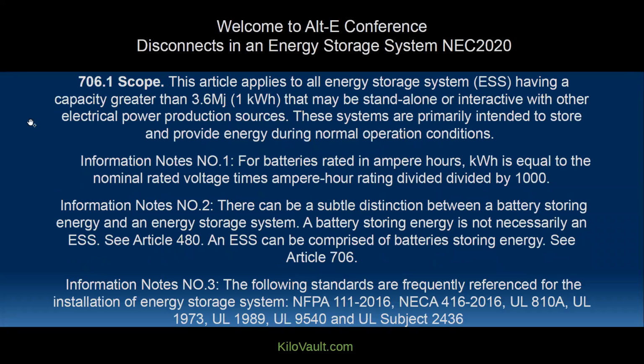So the scope of this article: an energy storage system is a capacity over 1 kilowatt, standalone or interactive with any energy source. Part of what we've got here is the ampere hours. Our second note is the distinction between a battery storing energy and a UPS system, which will be covered in Article 480. So we're covering more of the energy storage systems that are going to be cycled consistently, daily, weekly. A UPS center is more of a storage center designed to keep a computer bank or vital equipment up and running during a power outage. That's completely different from Article 706.